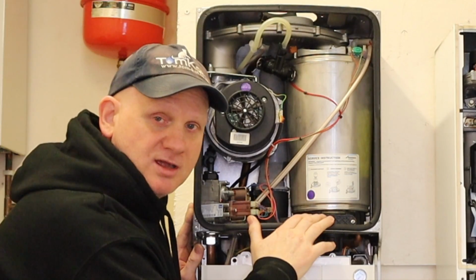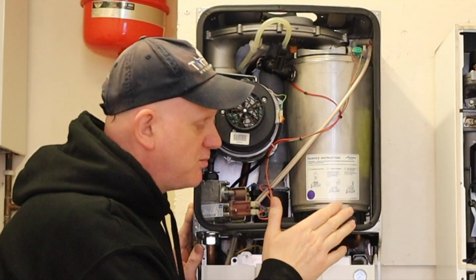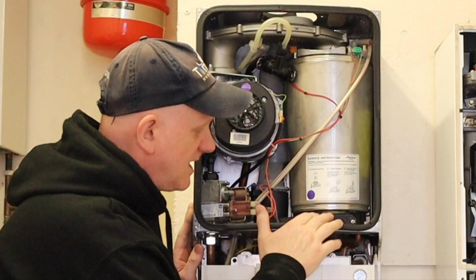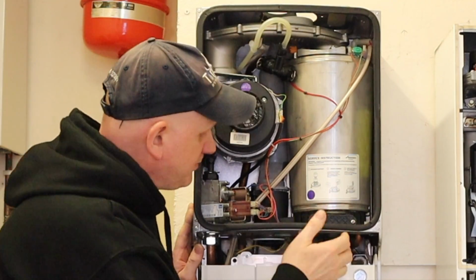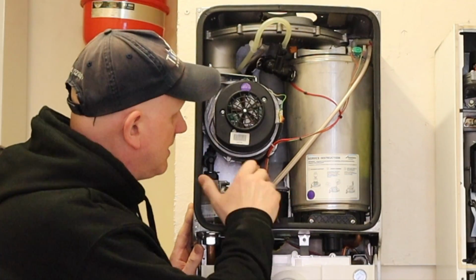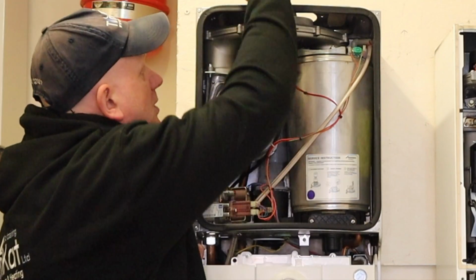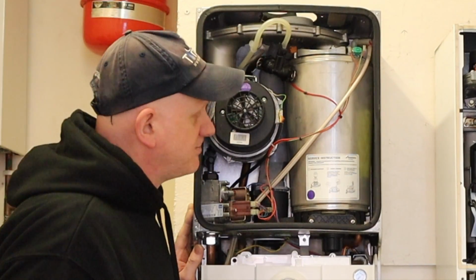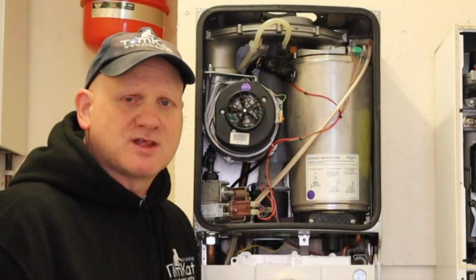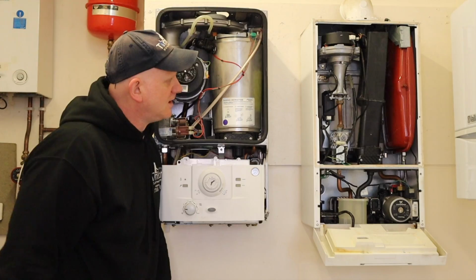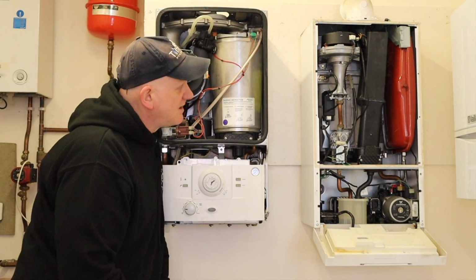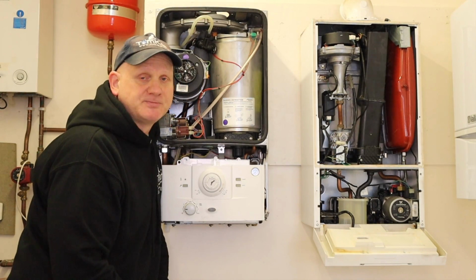But because it is a condensing boiler, the condensate then collects in the sump, which then goes down into the trap. The products of combustion then come up and out through the flue system. So that's basically the process of these working. Pretty much the same as this Ideal here.